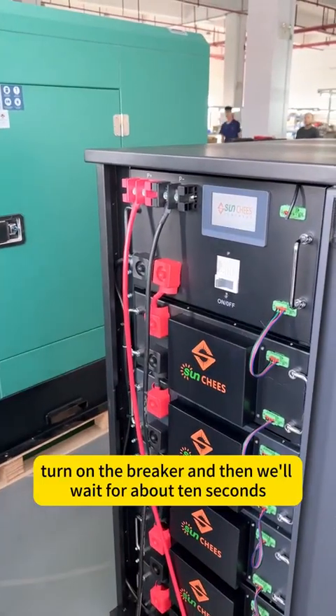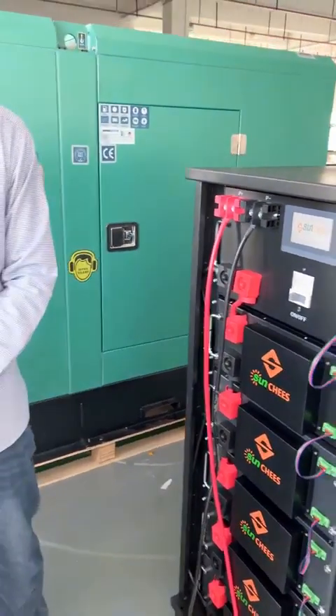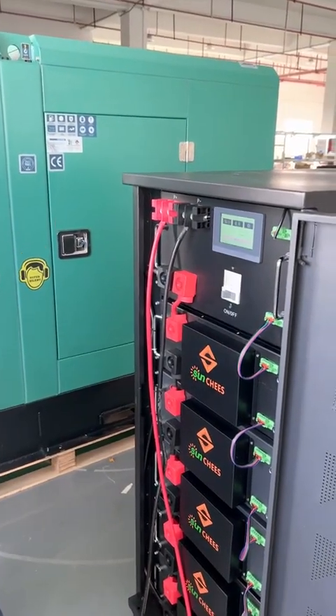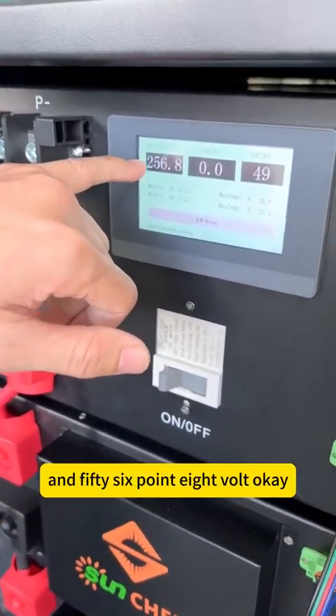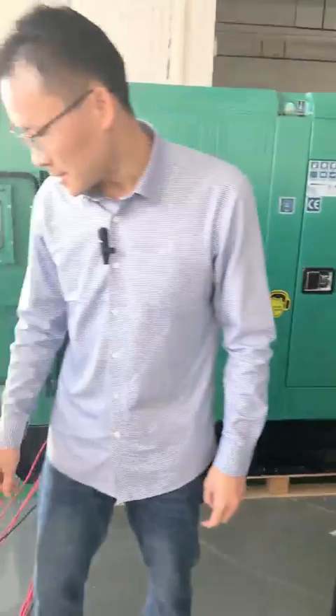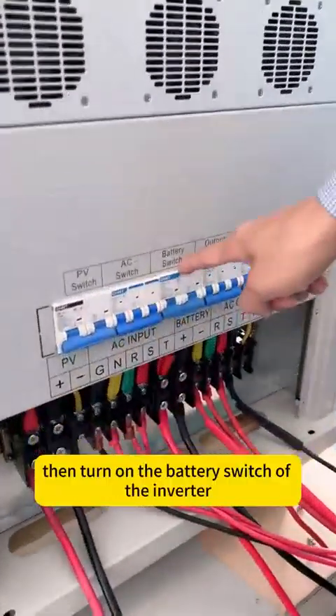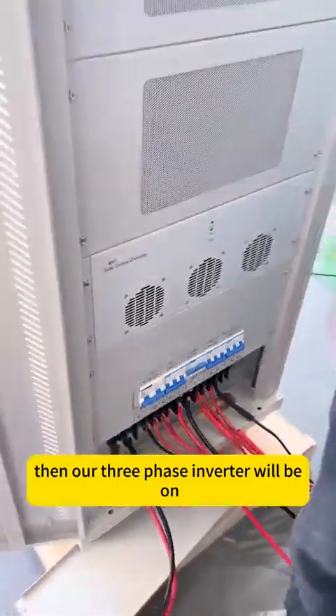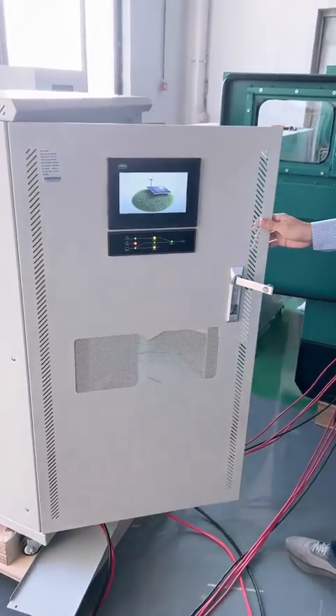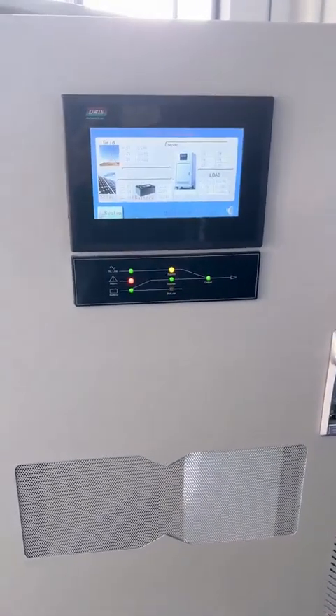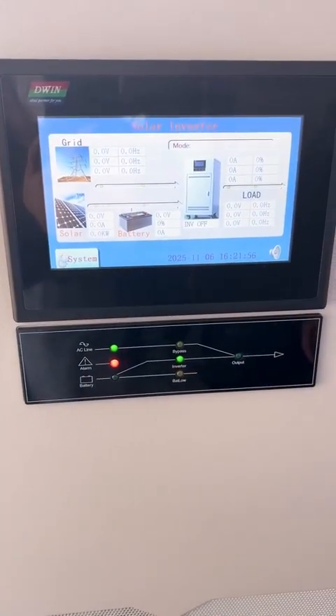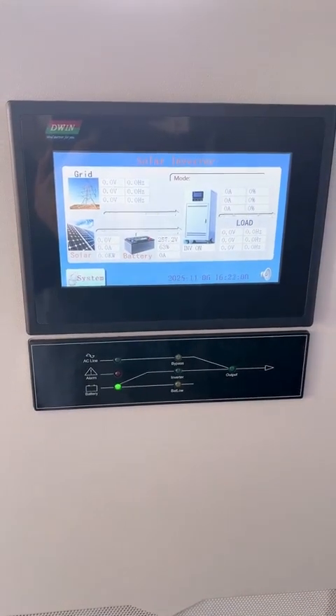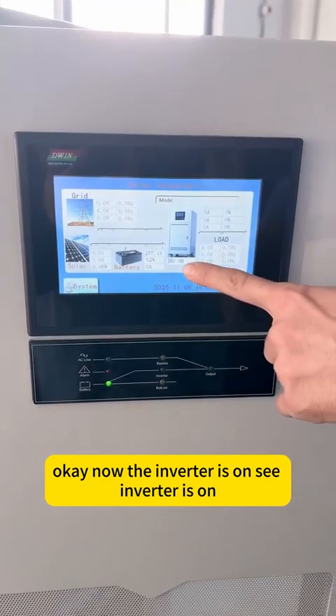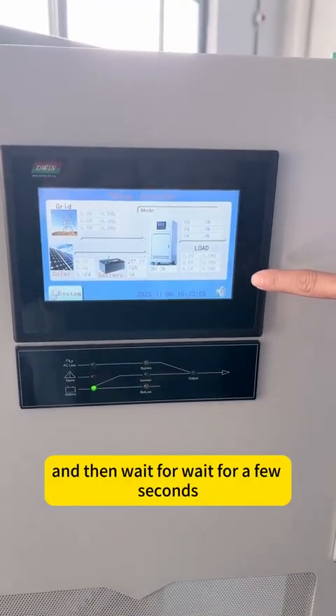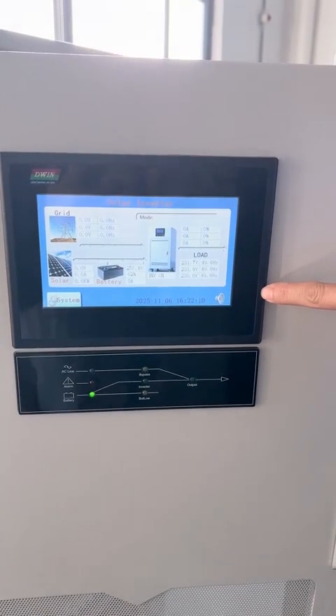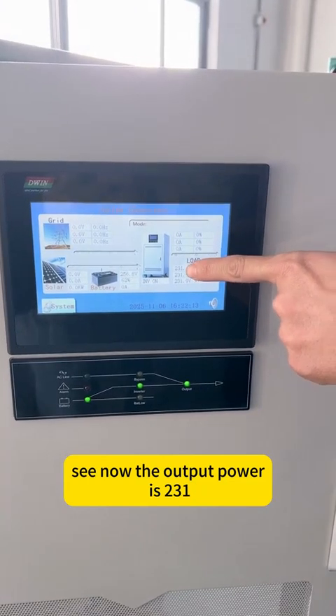Turn on the breaker, and then we'll wait for about 10 seconds. Now the lithium battery bank voltage is 256.8 volts. Then turn on the battery switch of the inverter. Then our three-phase inverter will be on. Now the inverter is on, and then wait for a few seconds. Now the output phase power is 231.